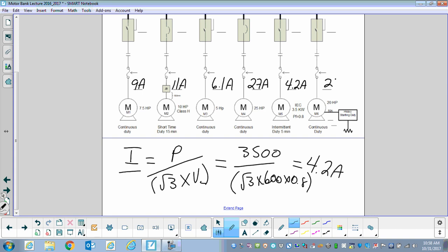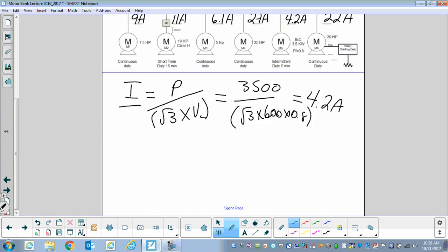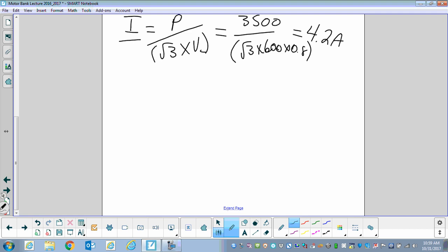We can put that up as 4.2 amps. Lastly, we have a 20 horsepower motor, which is 22 amps. Now that we have all full load currents, we need those numbers because a lot of what we do will be based off them. Let's now go to determining the branch circuit conductors.